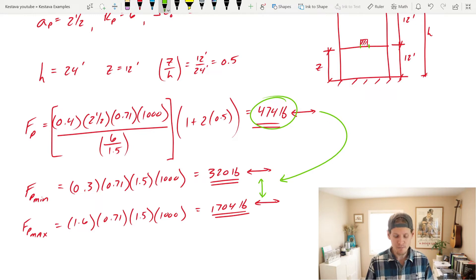If it does, you can continue to use the Fp that you've calculated. If it falls outside of those bounds, well, say if it's 1,800 pounds, well that means you only need to use a maximum of the 1,704 pounds. And if it's 200 pounds, then you need to use a minimum of the 320 pounds. But for us today, we are good to continue to use the 474 pounds.